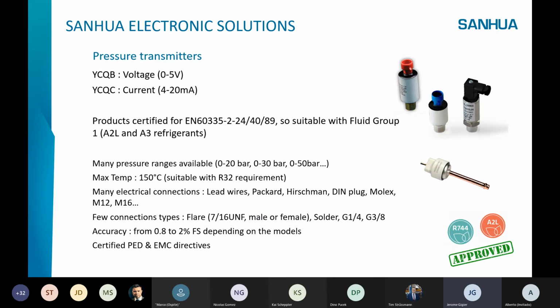About pressure transmitters, we have two models. We are certified for A2L. YCQB is a voltage model, and YCQC is for current, so 4 to 20 milliamp. This product is certified for group 1, so A2L and A3 refrigerant. We also have the certification.